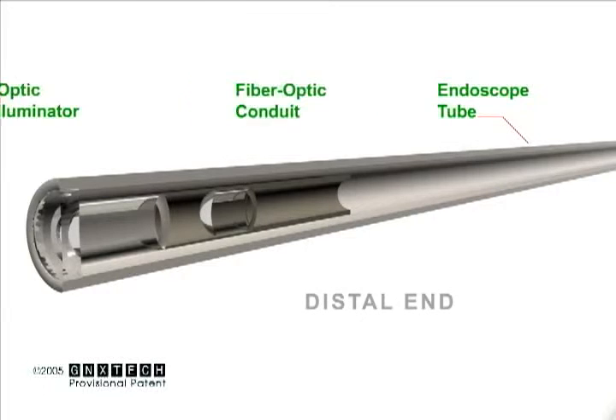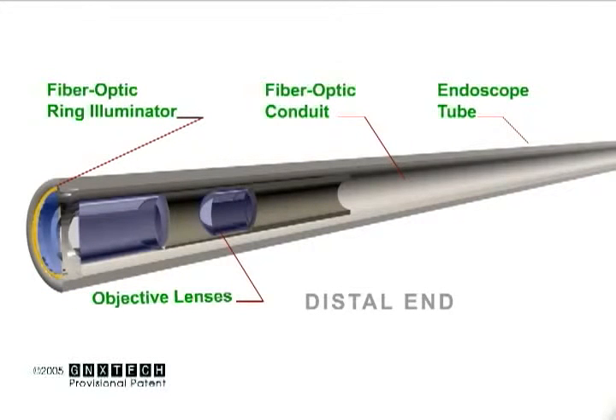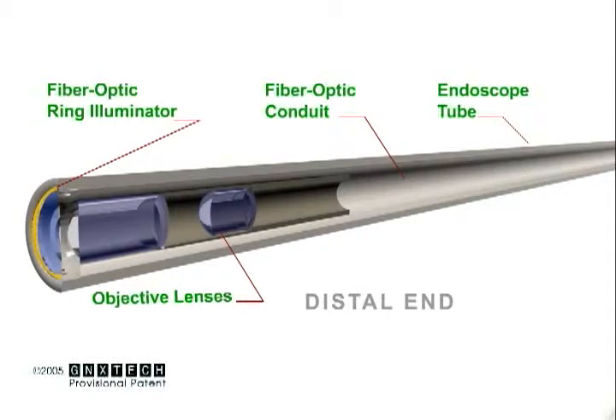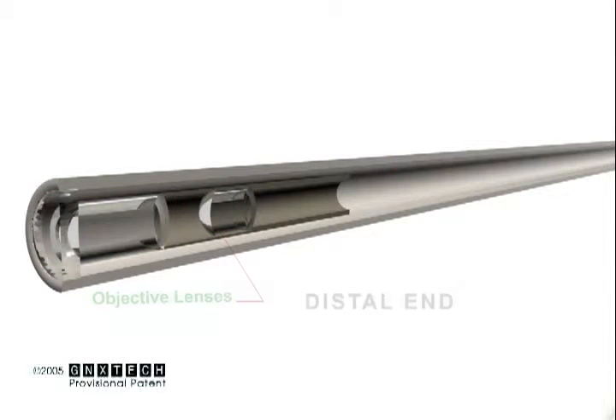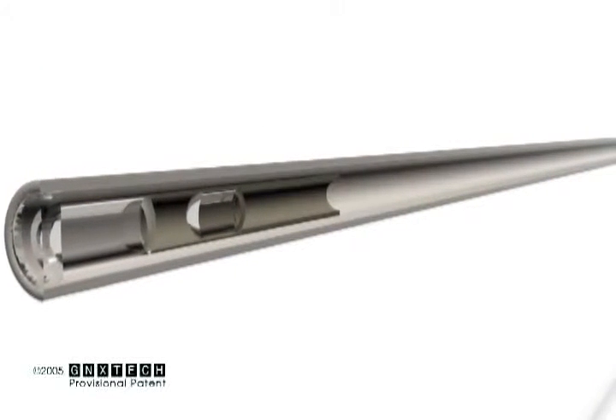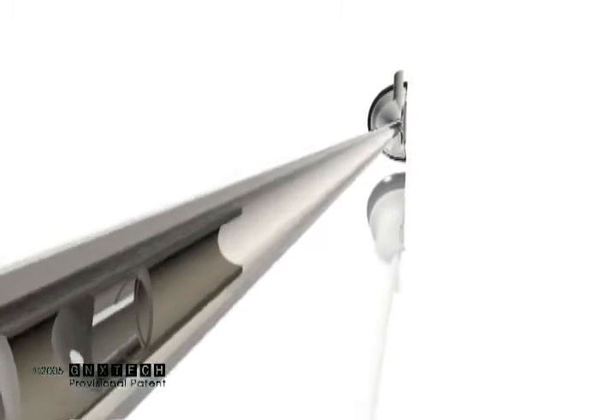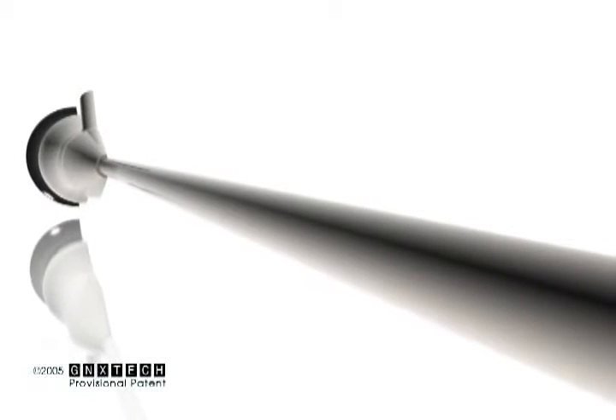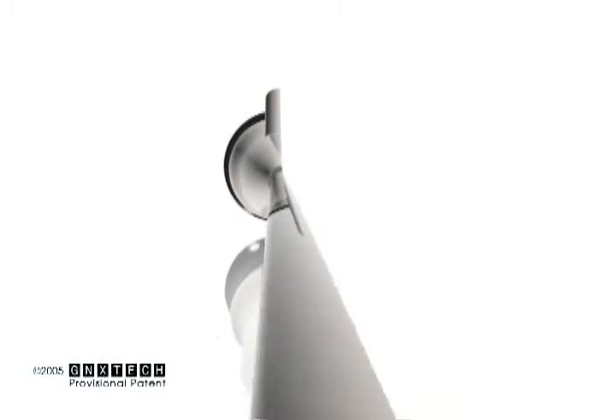A 4mm tube design has shown that objective lenses, image conduit, and illumination fibers can be combined to perform at high levels. The ring illumination at the distal end provides an even light pattern over the subject. An exact image of the subject field is then formed on the face of an imaging fiber optical conduit, and this image is transmitted through 50,000 plus internal fibers of the conduit to the proximal end of the endoscope.